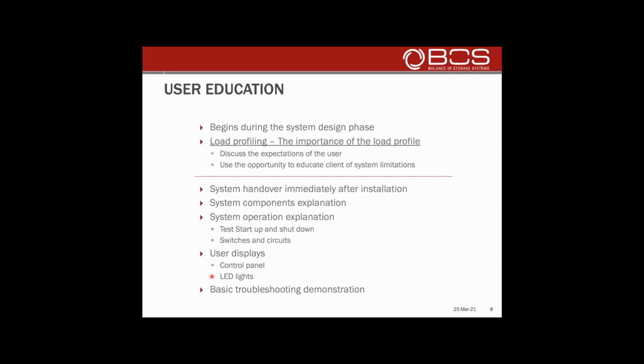Starting with the most basic element: user education. That begins at the sales or design phase. When discussing with a customer what size system they need, you go through their load profile, understand their expectations, and set expectations with them too, so they're not expecting to power something really big when you're sizing a system at half of that. Getting this part of the design correct at the very first stage, before anything is installed, can save a lot of headaches and difficult conversations later.